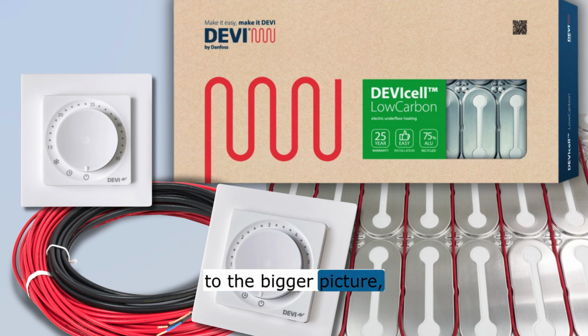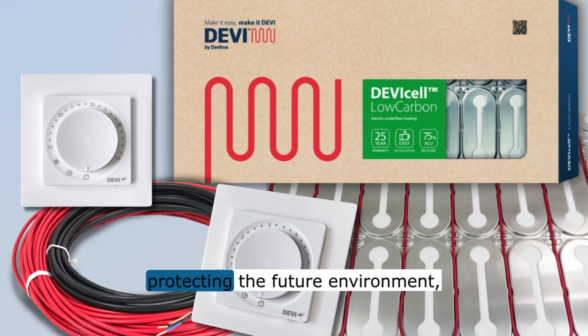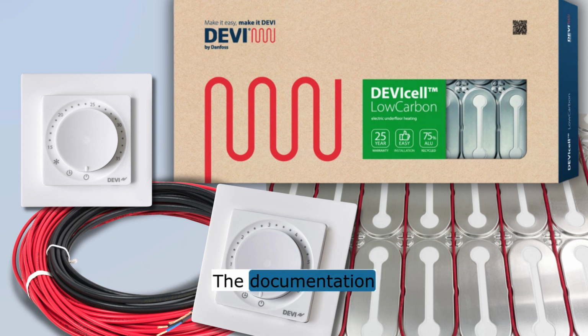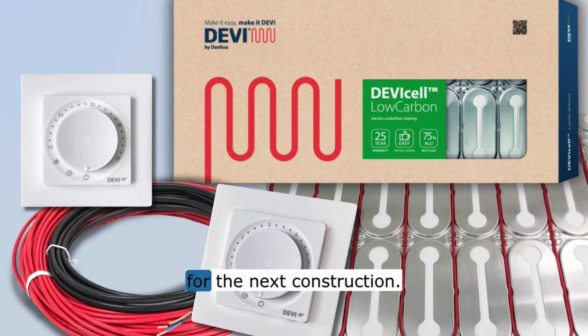If we connect this to the bigger picture, you're hitting on the core hazard of buried infrastructure. By making it hidden, you inherently create a trap for future renovations. The trap. Yeah, imagine 10 years from now, a new homeowner decides to bolt a heavy safe to the floor, or a plumber needs to jackhammer a section to fix a pipe. They have zero visual cue that there's a live electrical grid 2 inches below the tile. And that's how people get electrocuted. They need those warnings in the fuse box before they ever touch a tool. Without that documentation, they risk drilling a steel bit straight into a live 230-volt cable. So the safety rules here are about protecting the environment and the people 10 or 20 years down the line. Exactly. You're protecting the future environment, not just the current installation. The documentation is basically a map through a minefield for the next contractor.